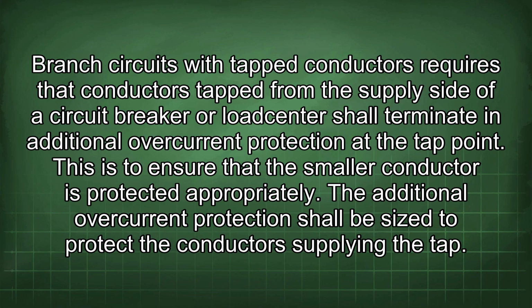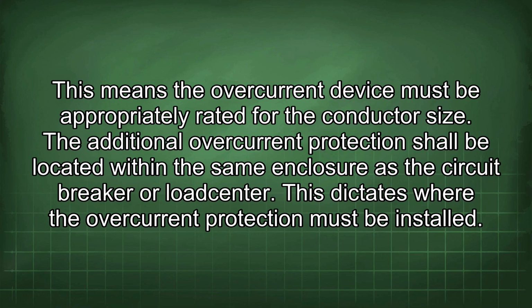The additional overcurrent protection shall be sized to protect the conductor supplying the tap. This means the overcurrent device must be appropriately rated for the conductor size. The additional overcurrent protection shall be located within the same enclosure as the circuit breaker or load center. This dictates where the overcurrent protection must be installed.